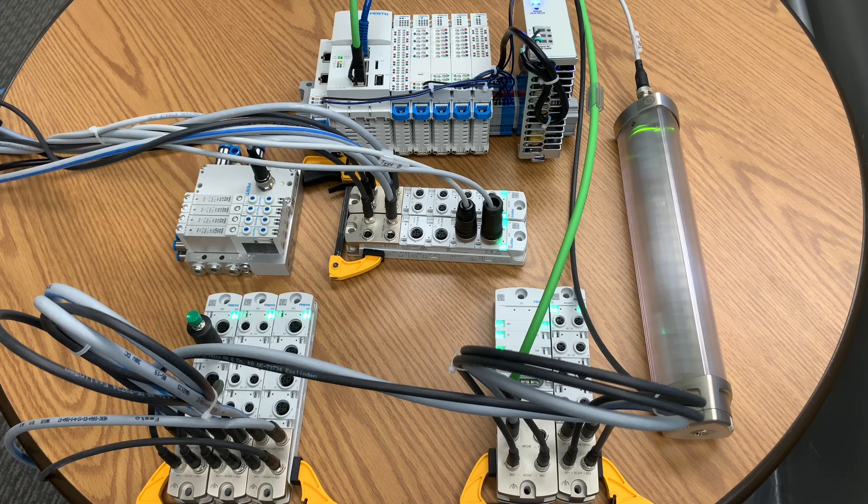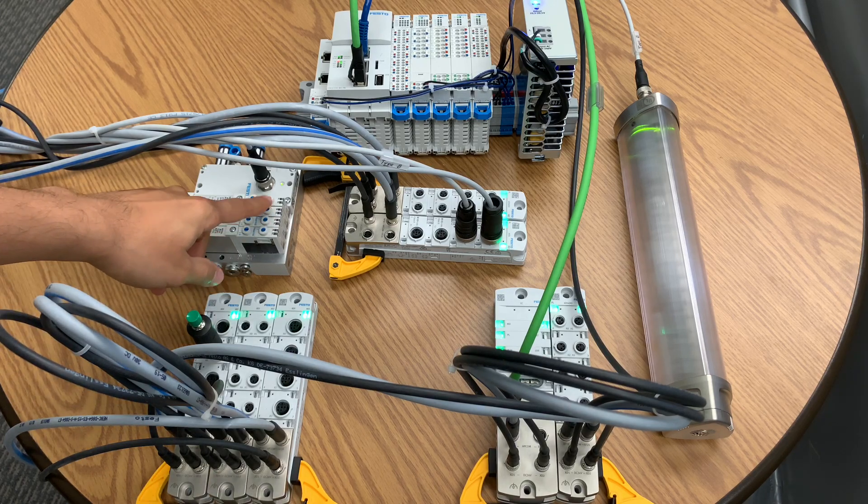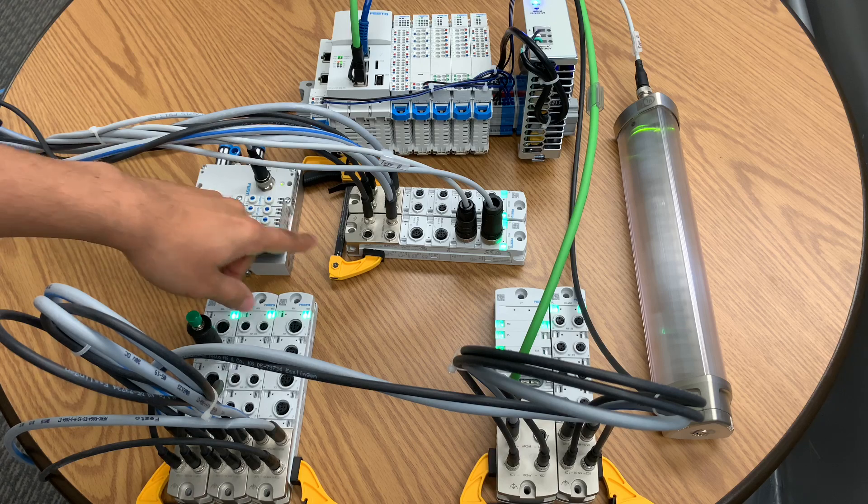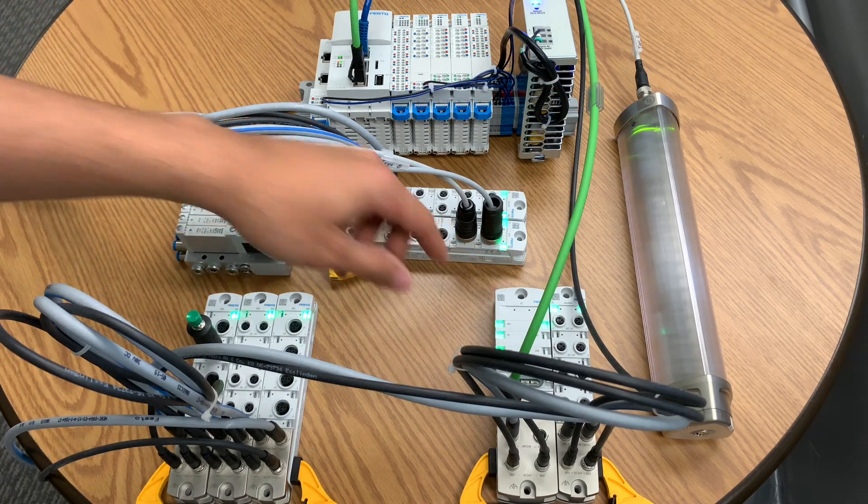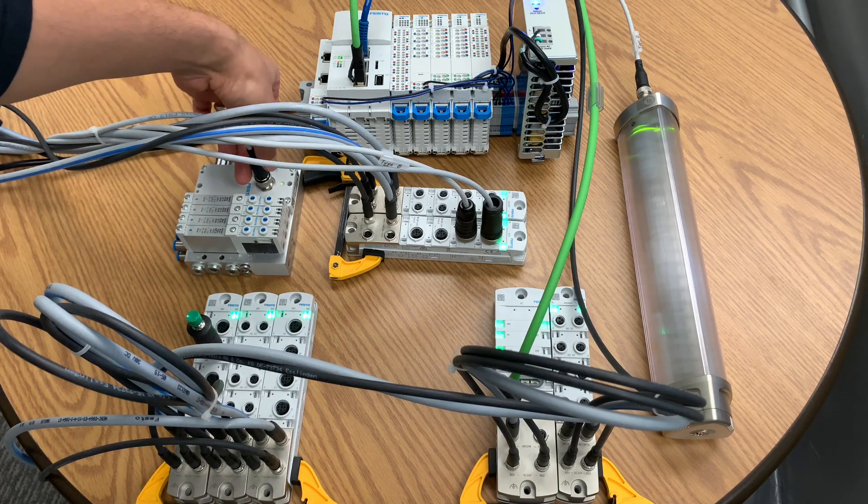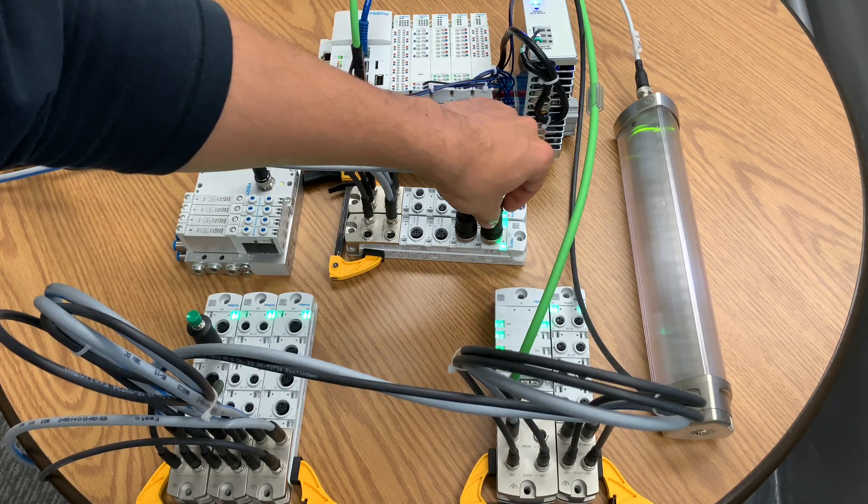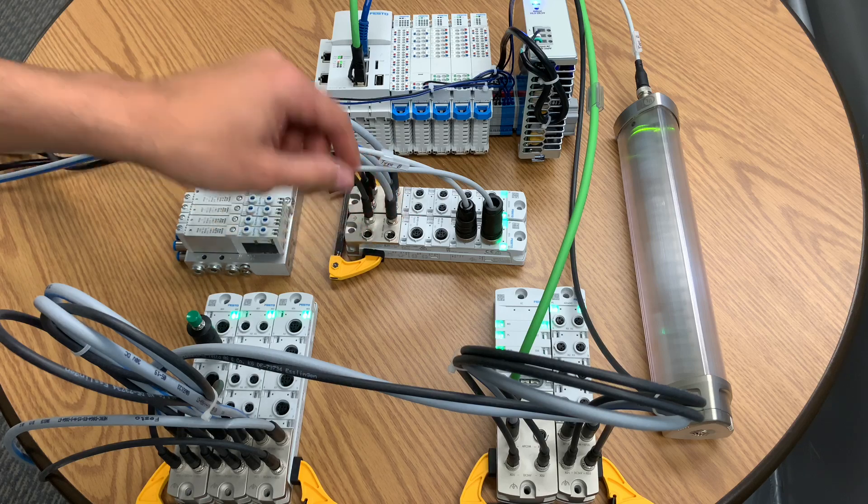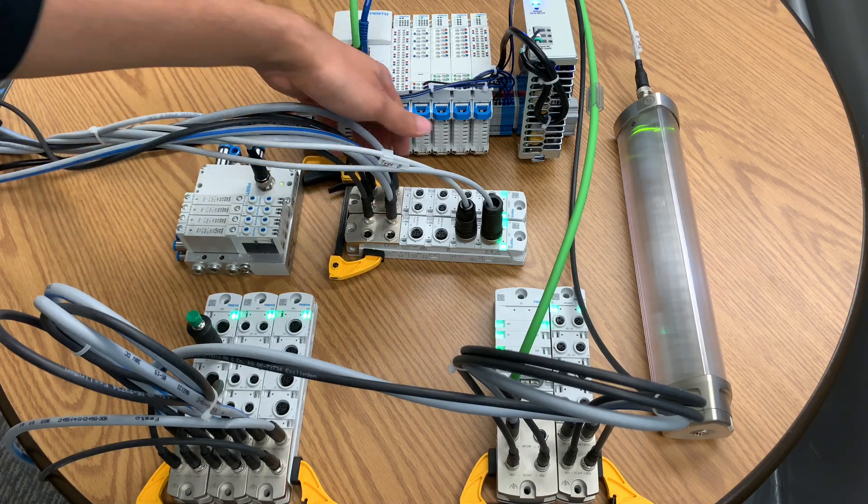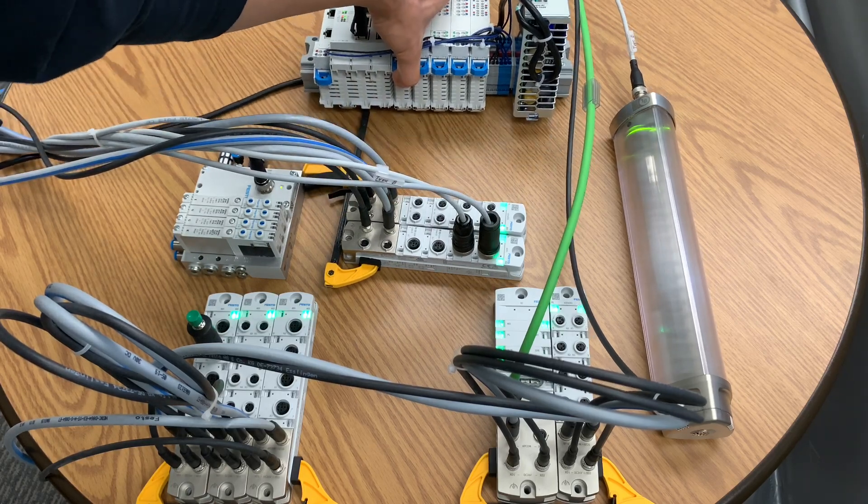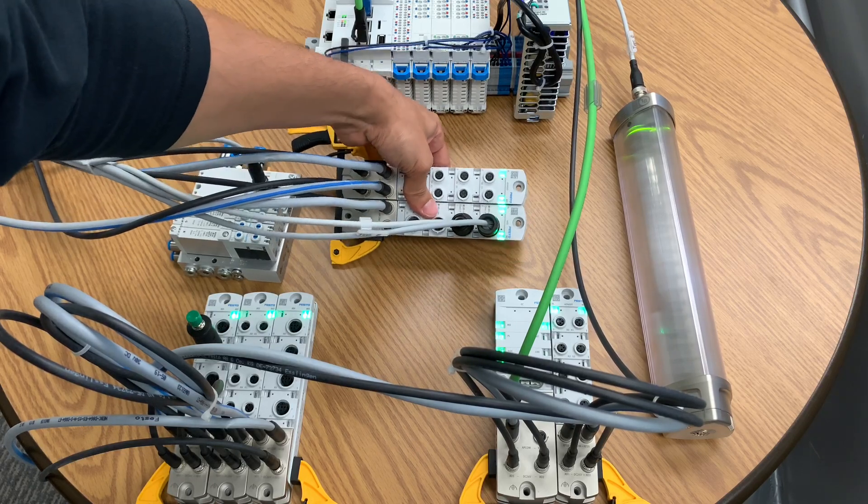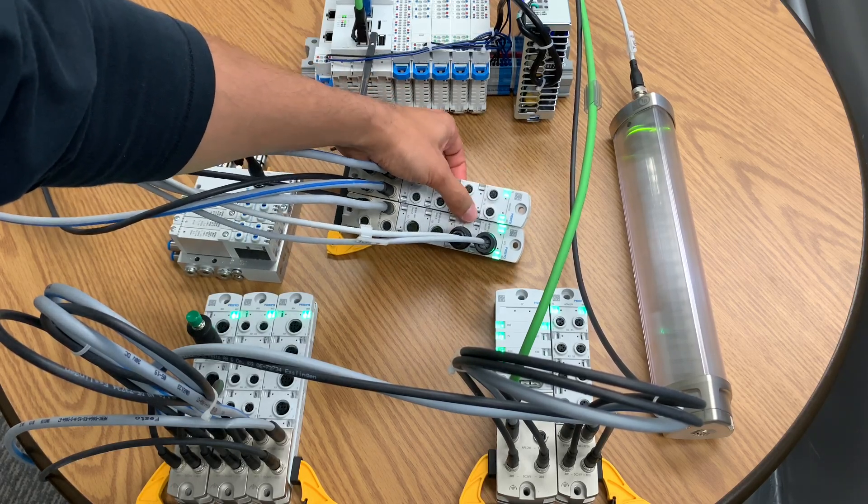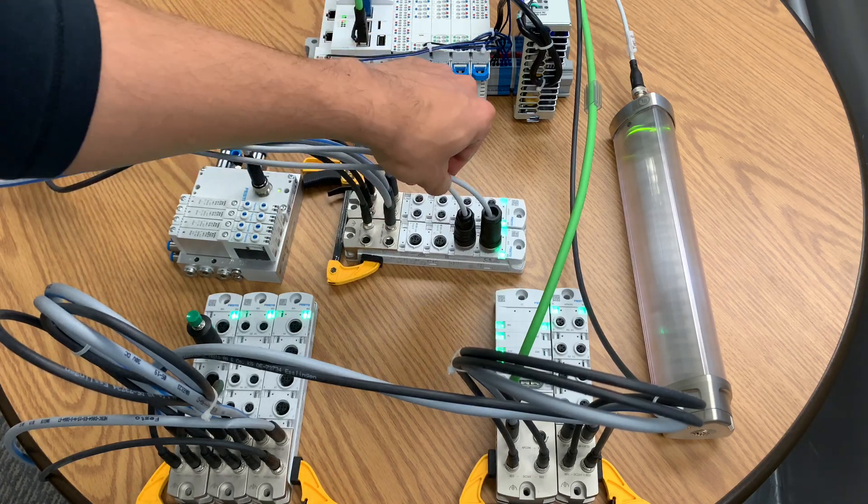Now if I wanted to switch on some of these coils on this manifold, what I would have to do is use the bytes on this IO link master, because this cable on the manifold is connected over IO link to this very first port. The first thing I have to do though, is enable the IO link ports. Right now they are disabled by default. Let me bring this out so I can turn it around. You can see these LEDs right here. These ones are off. So I have to enable those ports.